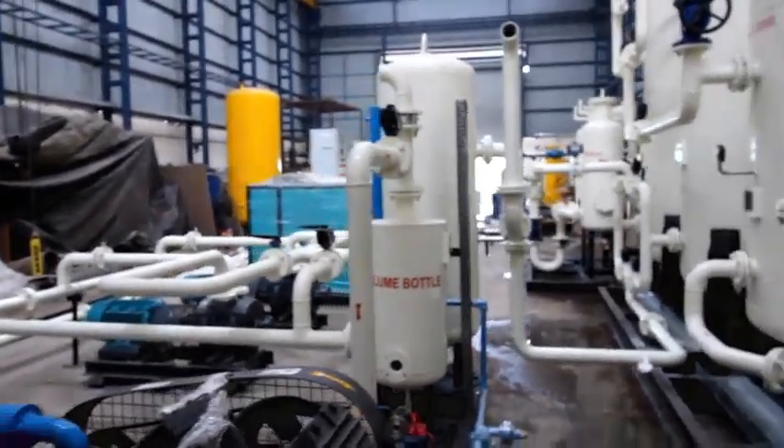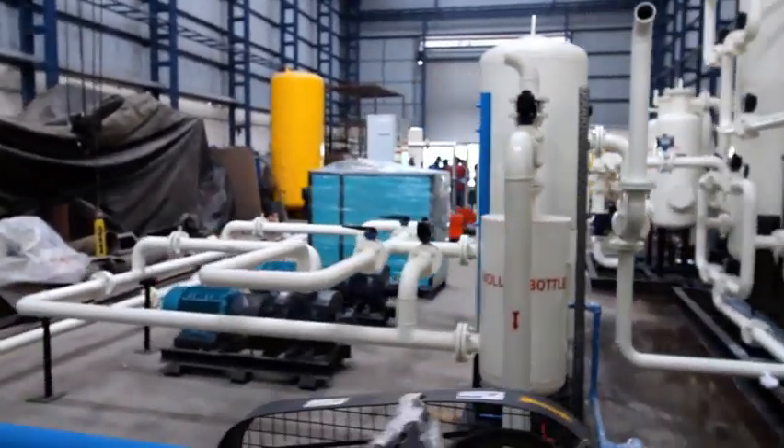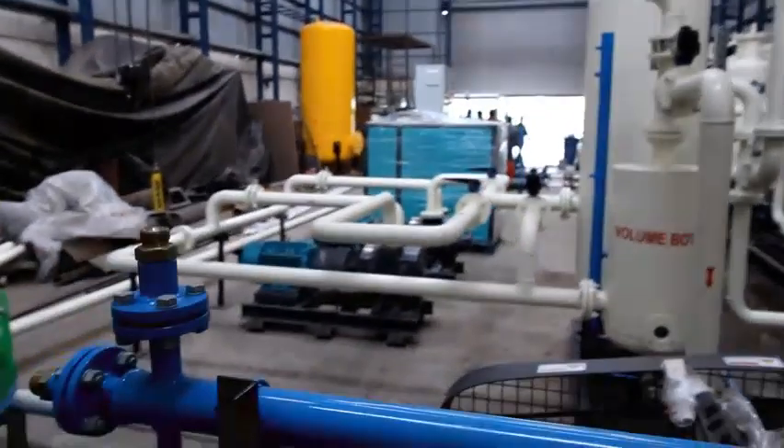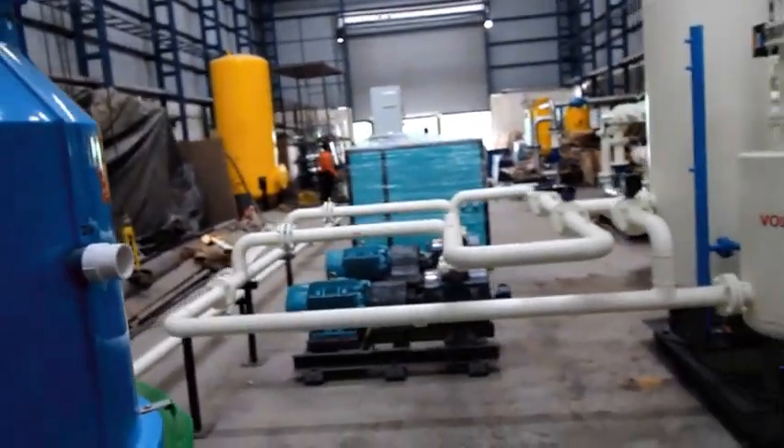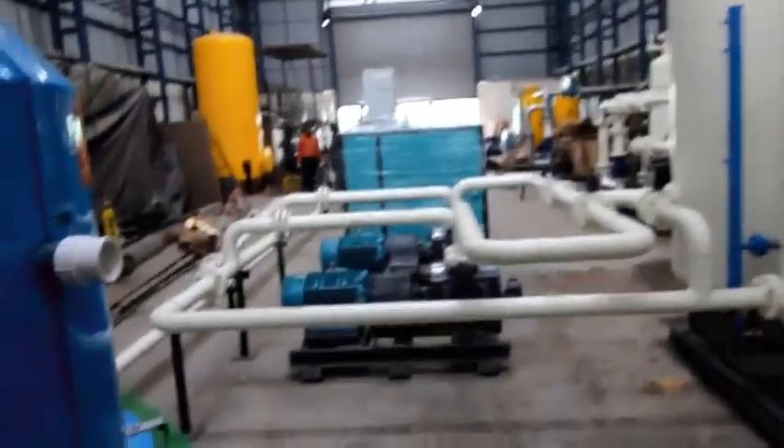The regeneration of molecular sieves is achieved by depressurizing the VPSA towers and removing the adsorbed gas by vacuum with the help of a vacuum pump. After a preset time, the process switches from one tower to another via auto changeover valves, controlled by a signal from the PLC.